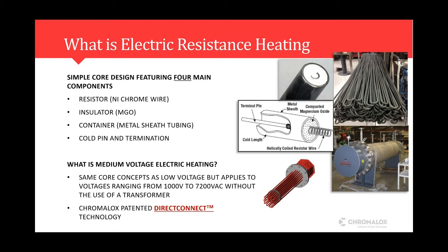Magnesium oxide is used because it has excellent dielectric strength, but it also has excellent thermal conductivity properties. So the key to the life of an electric heater element is to have the electric resistance wire run as cool as possible at the inner core. If you get to high temperatures or you have magnesium oxide that is not compacted properly, it will ground out easily to the metal sheath tubing, as you see here.